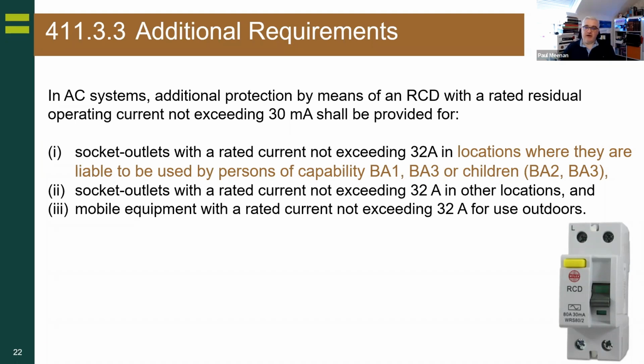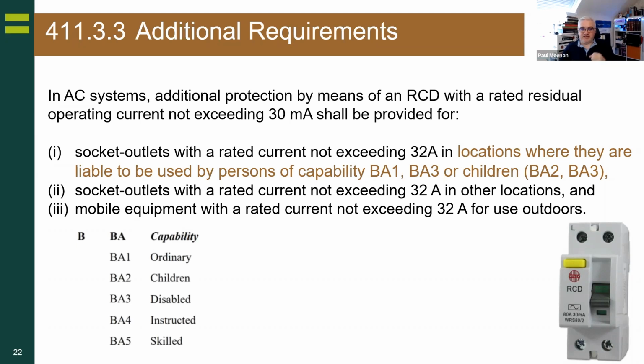...assess yourself out. What they've done is add a little bit of clarity into this reg, and I think it's a great improvement. So what they've said is socket outlets of a rated current not exceeding 32 amps in locations where they're liable to be used by persons BA1, BA2, or BA3. And later on in the appendices, there's a little table, utilizations, and it gives you clearly ordinary persons, children, disabled persons. So a little bit of good knowledge there to just make people aware.